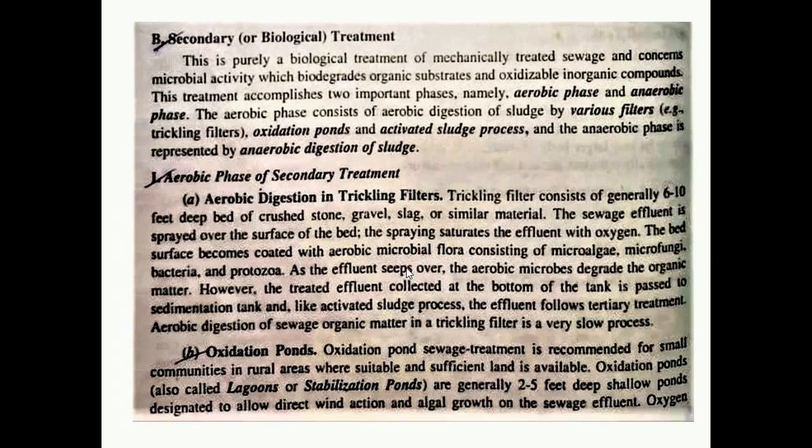Next one, oxidation ponds. Oxidation pond sewage treatment is recommended for small communities in rural areas where suitable and sufficient land is available. Oxidation ponds, also known as lagoons or stabilization ponds, are generally 2 to 5 feet deep shallow ponds designed to allow direct wind action and algal growth on the sewage effluent.